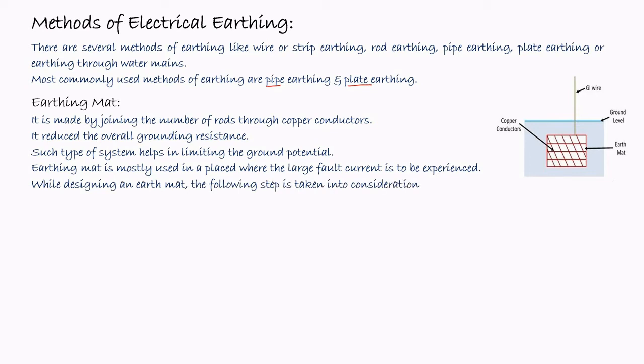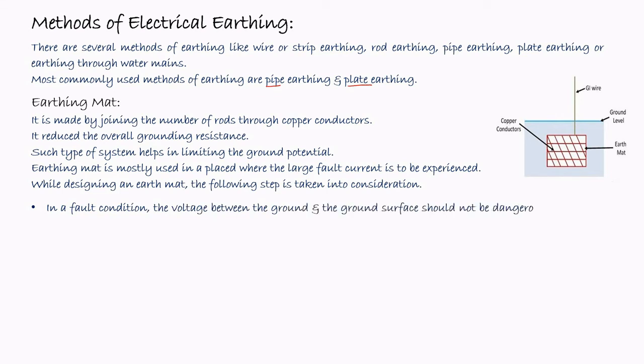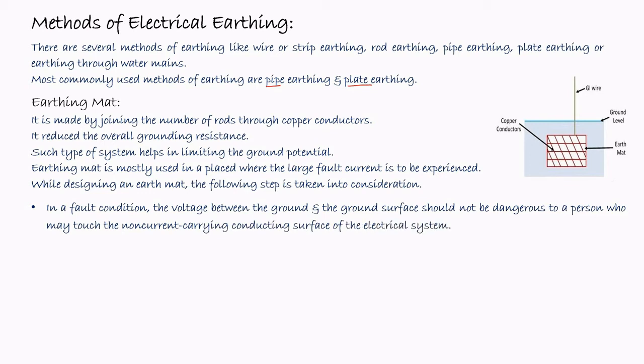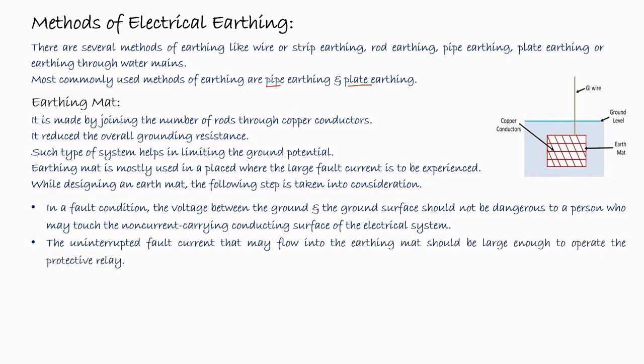Now, while designing an earth mat, the following steps are to be taken into consideration. First, in a fault condition, the voltage between the ground and the ground surface should not be dangerous to a person who may touch the non-current carrying conducting surface of the electrical system. Next, the uninterrupted fault current that may flow into the earthing mat should be large enough to operate the protective relay, that means the relay which is connected with the earth leakage circuit breaker. The resistance of the ground should be low to allow the fault current to flow through it. So the resistance of the ground should be as low as possible so that the current can easily flow through the earthing wire to the ground.